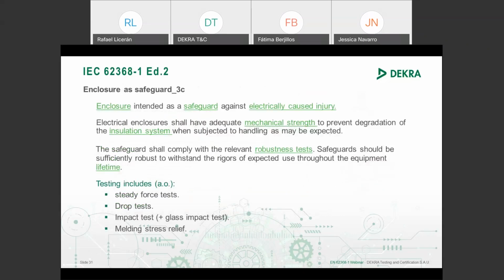If you use the enclosure as a safeguard, take into account that this standard has a new annex. This is Annex T, Tango, which includes all mechanical requirements for the enclosure of the device. This requirement is very similar to the 60950 or 60065 requirement. It changes a bit only in stability tests and so on, which we check afterwards.